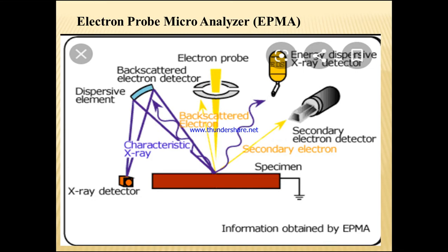An electron microprobe operates under the principle that if a solid material is bombarded by an accelerated and focused electron beam, the incident electron beam has sufficient energy to liberate both matter and energy from the sample. These electron-sample interactions mainly liberate heat, but they also yield derivative electrons and X-rays, namely the secondary electrons, backscattered electrons, and characteristic X-rays.